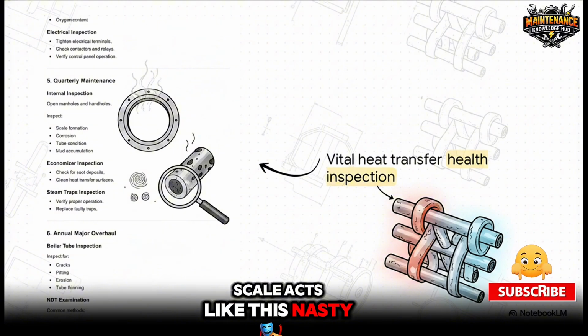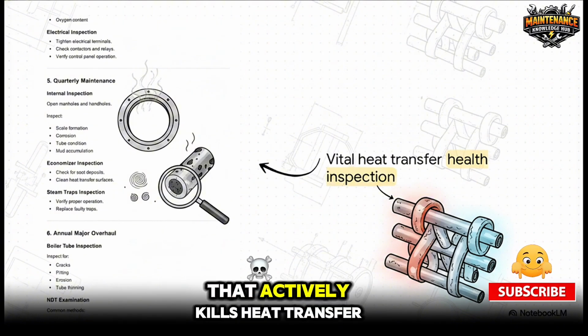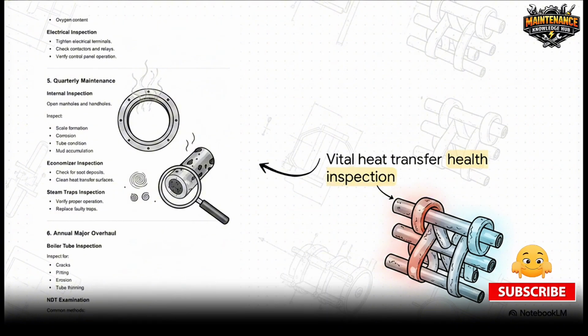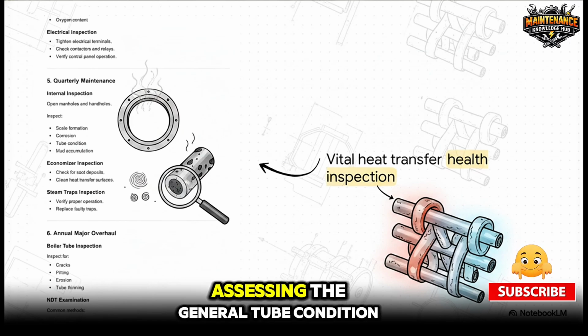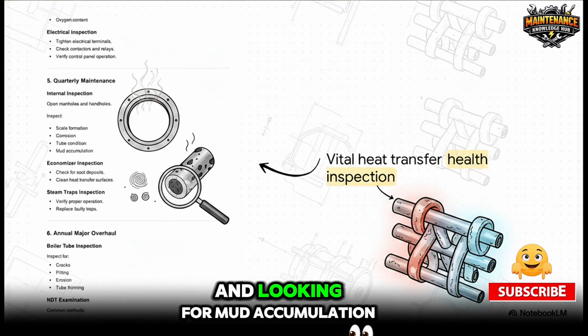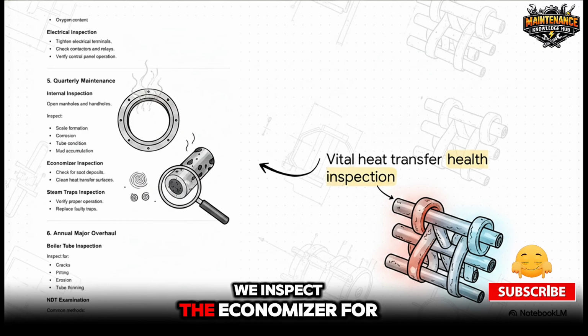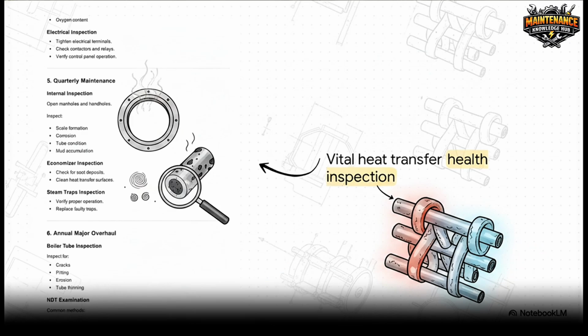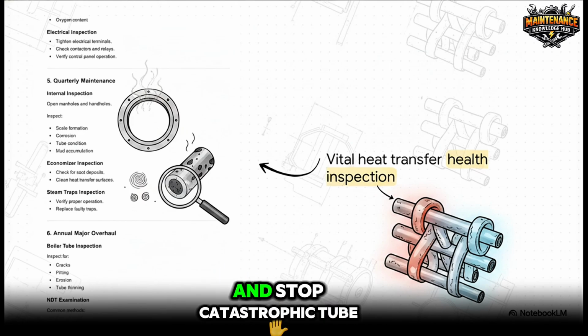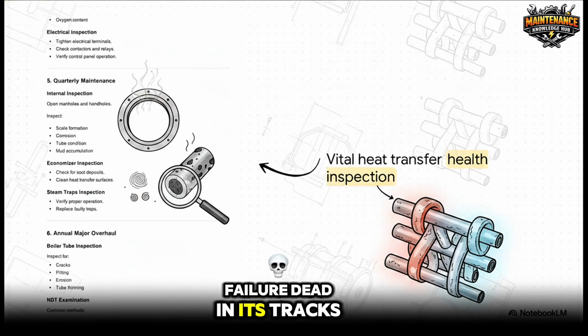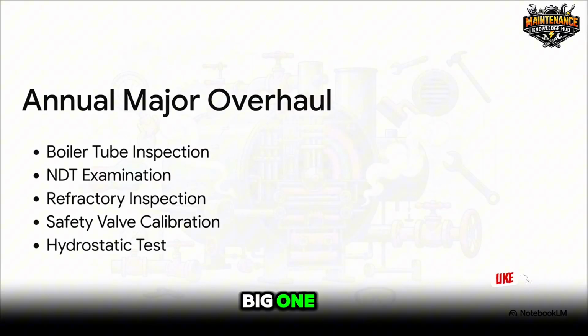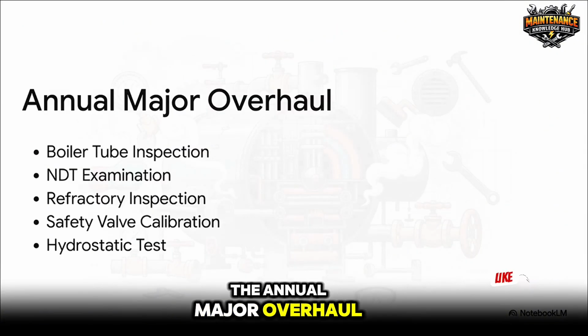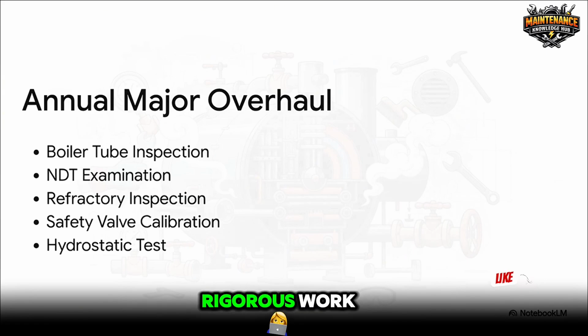Scale acts like this nasty parasitic blanket on your tubes that actively kills heat transfer. We're also checking for active corrosion, assessing the general tube condition, and looking for mud accumulation. We inspect the economizer for soot deposits and scrub those heat transfer surfaces clean. If you catch that parasitic scale early, you literally save a ton of fuel and stop catastrophic tube failure dead in its tracks. And then comes the big one, the annual major overhaul. This is super thorough, rigorous work.